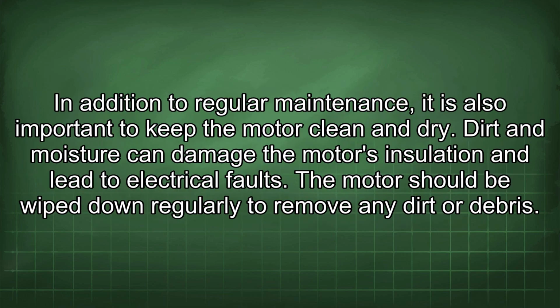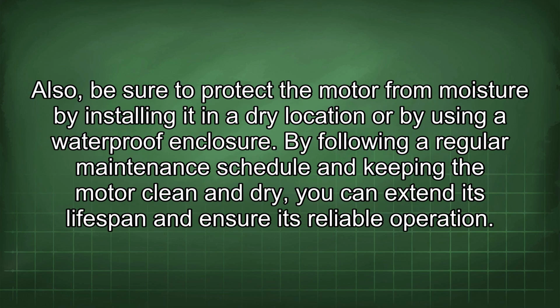In addition to regular maintenance, it is also important to keep the motor clean and dry. Dirt and moisture can damage the motor's insulation and lead to electrical faults. The motor should be wiped down regularly to remove any dirt or debris. Also, be sure to protect the motor from moisture by installing it in a dry location or by using a waterproof enclosure. By following a regular maintenance schedule and keeping the motor clean and dry, you can extend its lifespan and ensure its reliable operation.